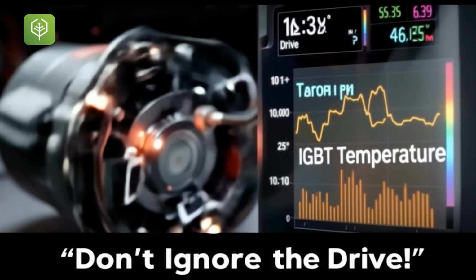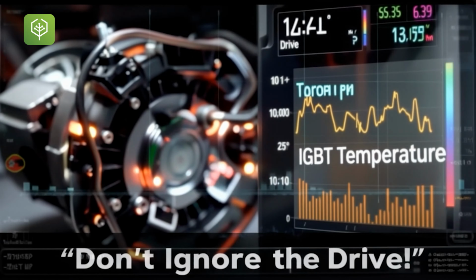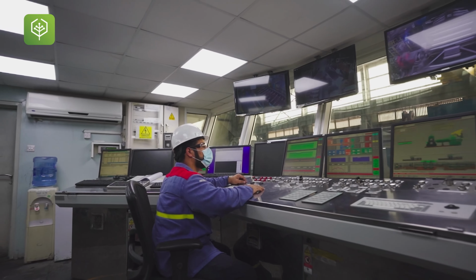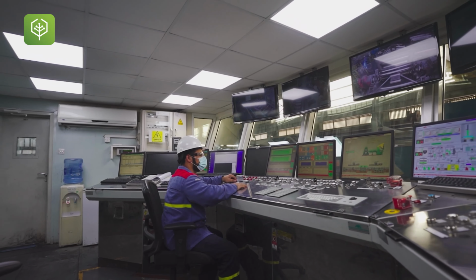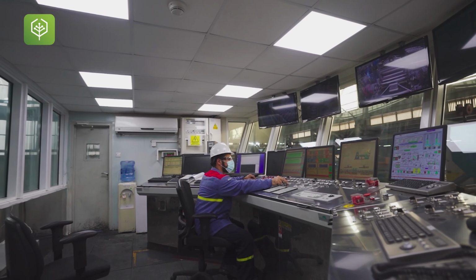So this was the motor part, but nobody cares about the drive system which is running the motor. In G120 we can get the IGBT temperatures, the torque, the RPM as I mentioned earlier. From that we can also monitor the drive system. Motor can fail, but the power module which is running your motor can also fail. If the motor is good but your drive system is bad, you also need to monitor your drive system. For unproductivity, the drive is as much a culprit as the motor. So motor can fail and drive can also fail. Nobody is thinking about monitoring a drive system.